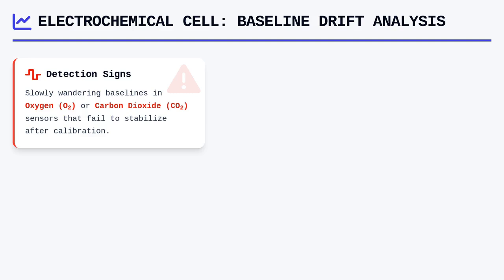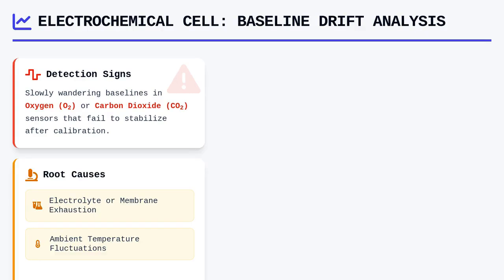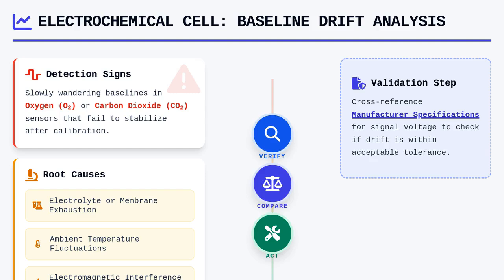In the domain of electrochemical cells, detecting constant baseline drift is a routine but critical task that often points to sensor exhaustion or unstable environmental variables. If your oxygen or carbon dioxide sensors exhibit a slowly wandering baseline that refuses to stabilize after a standard calibration, you must first verify the chemical life of the electrolyte or the membrane status. Consistent drift suggests that the sensor is no longer capable of reaching equilibrium, which is frequently caused by ambient temperature fluctuations or interference from electromagnetic sources near the circuit board. Always cross-reference the manufacturer's specifications for the expected signal voltage to determine if the drift is within tolerance or if a complete replacement is required.